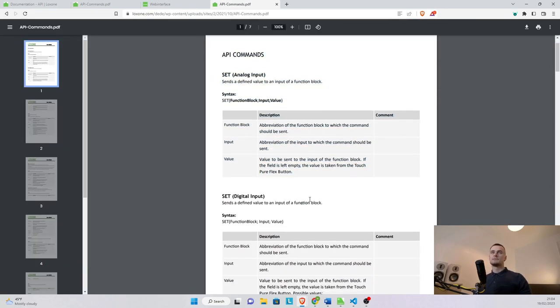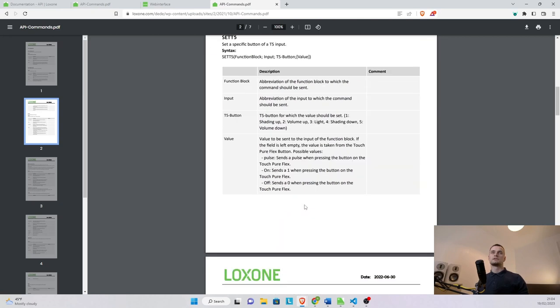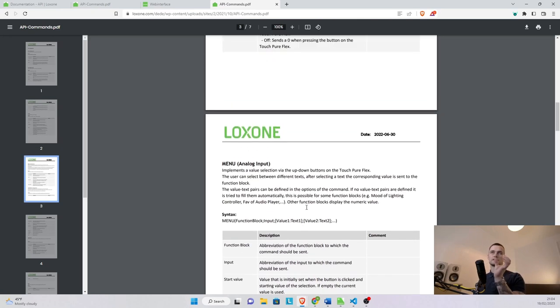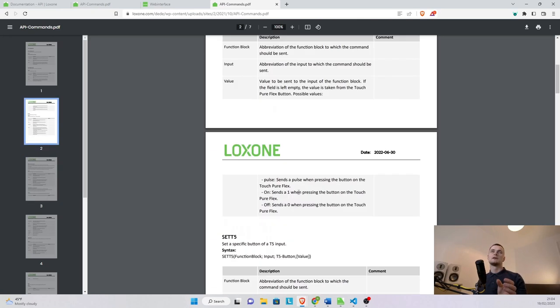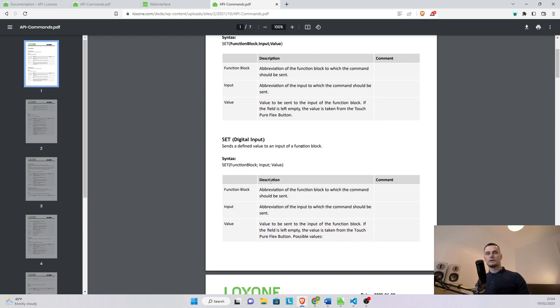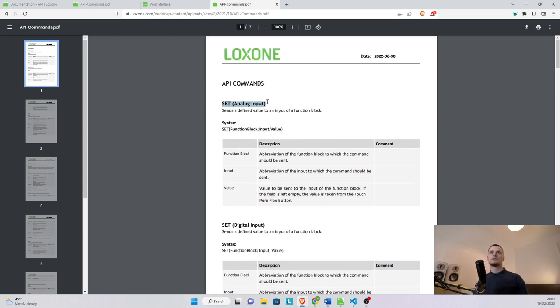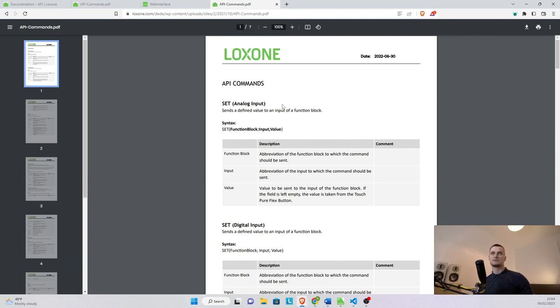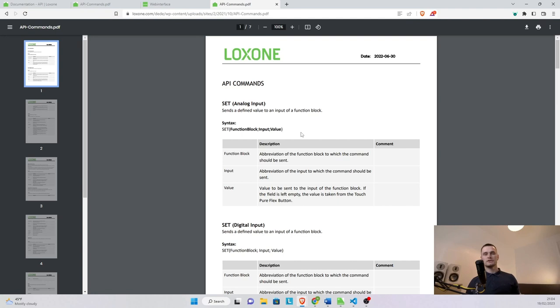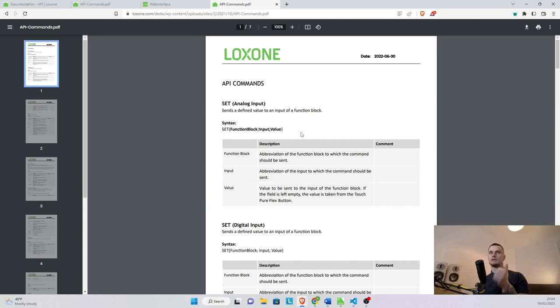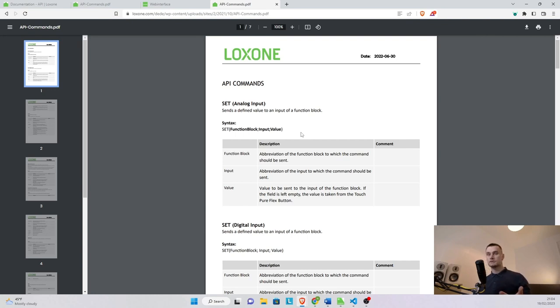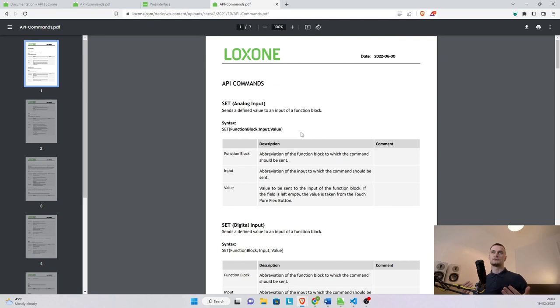Now in here in this pdf you can see the information and the structure of every single command. The command that we're going to use today to show is going to be the set command and we're simply going to switch the lights on, switch the lights off and also show you how to operate a switch block, toggle it on and off whatever the command is being sent. Now as you can see here's the syntax that's being used. You need the name or the short description of the function block, you need the input and you need the value that we're sending to it. The value can be depending on what the input is obviously one or zero, it can be a pulse or it can also be zero to a hundred percent depending on what you're using it for.